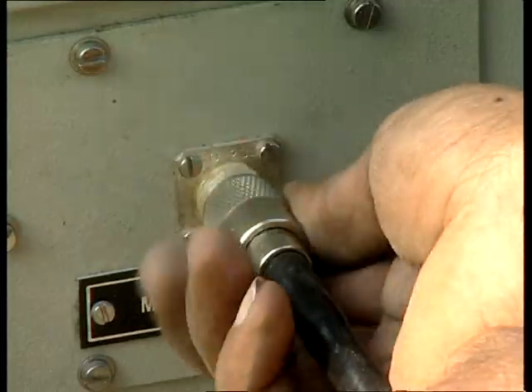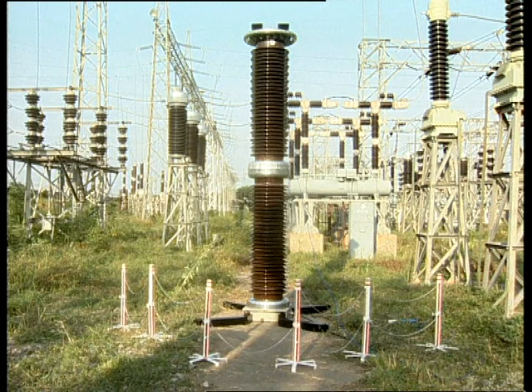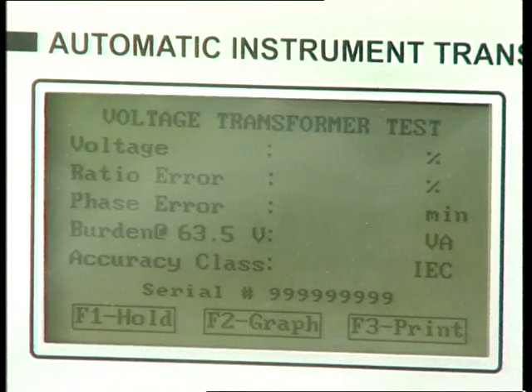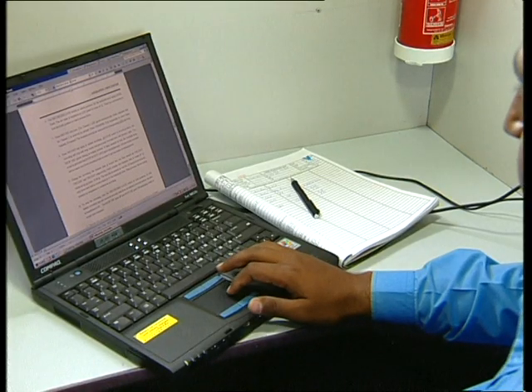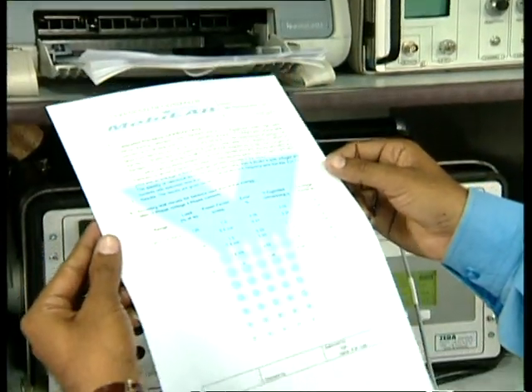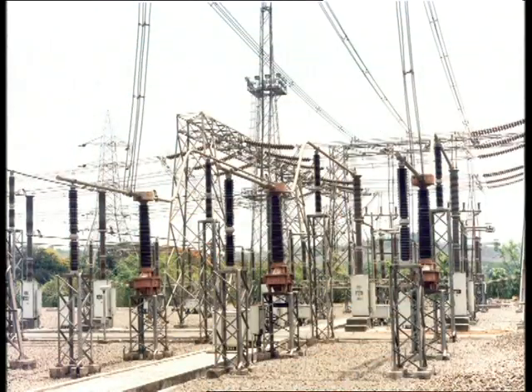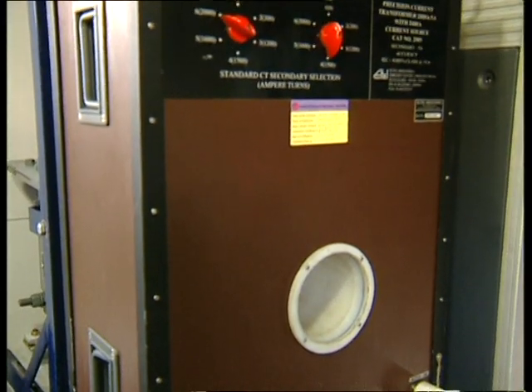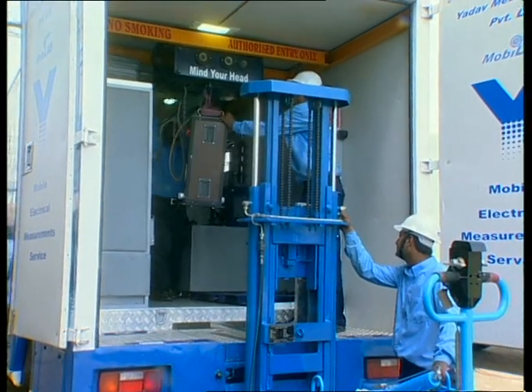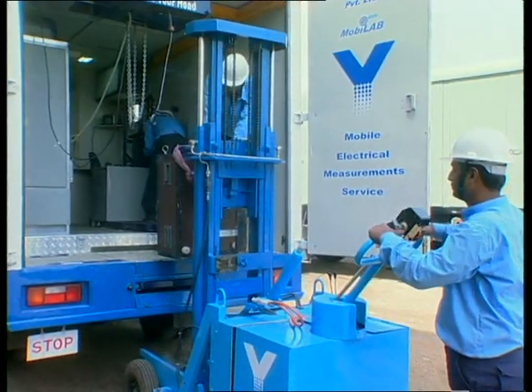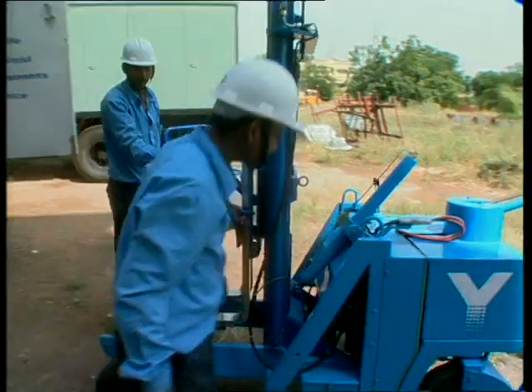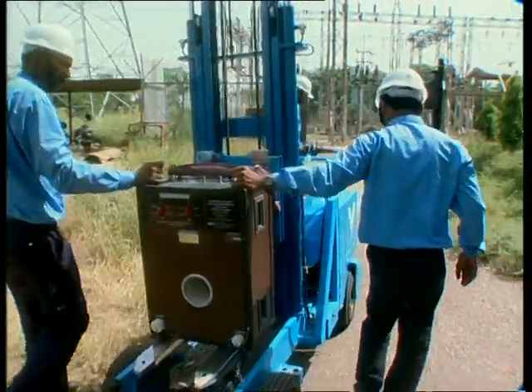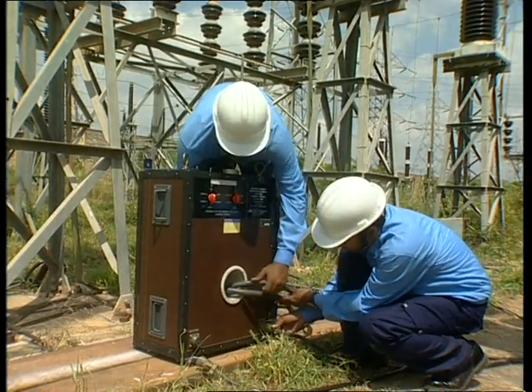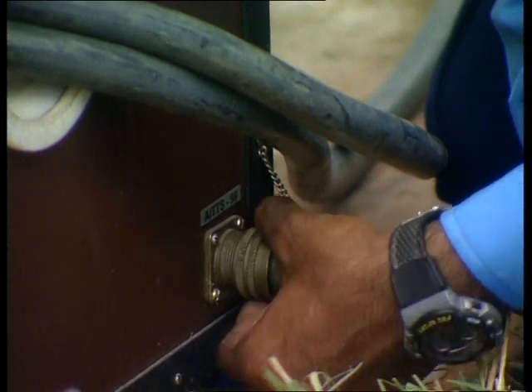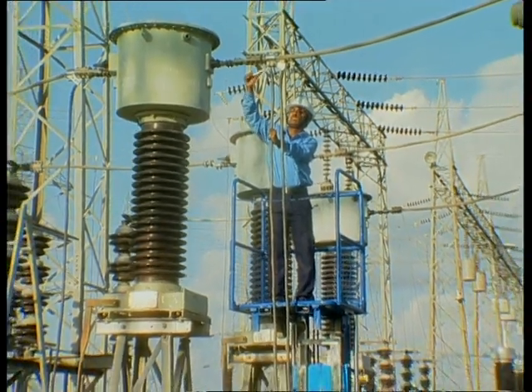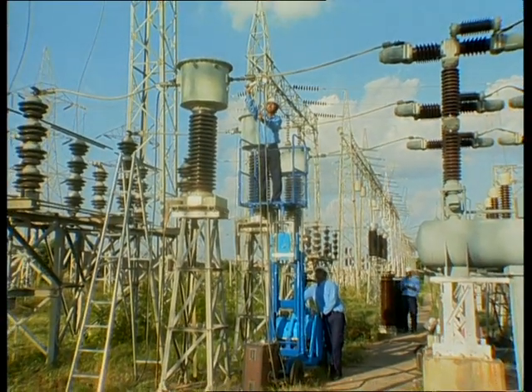Once the equipment is set up, the relevant section of the substation needs to be shut down and the test equipment wired up. The test itself takes a few minutes. Test results are stored in the equipment and downloaded to the on-board computer in MOBILAB to produce valid calibration certificates on the spot. The heart of the current transformer or CT calibration system is a standard CT with source. The CT test system has an accuracy of 0.03% and is suitable for CT primary current up to 2000 amperes with a capacity of 6000 volt amperes. Since CT errors are greatly influenced by the burden connected to them, testing CTs under real burden conditions is a great advantage. Conducting a CT test is a matter of setting up the test equipment at site.